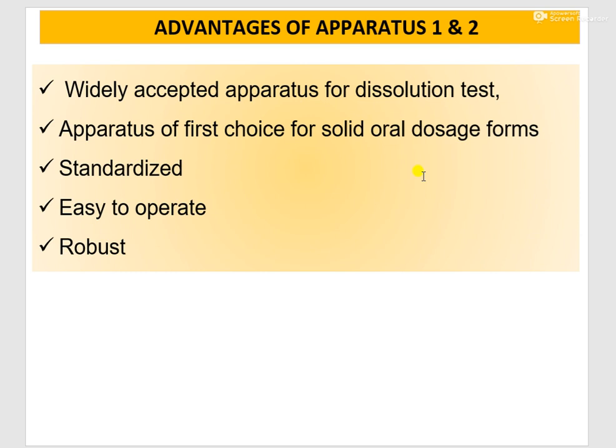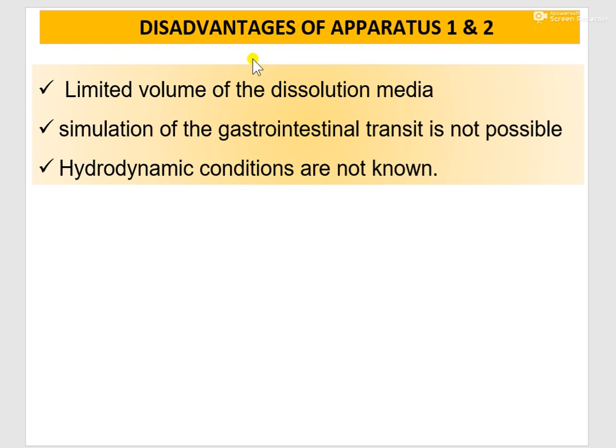Regarding advantages of apparatus 1 and 2: both are widely accepted and commonly used apparatus for dissolution testing, serving as the apparatus of first choice for solid oral dosage forms. They are standardized, easy to operate, and robust. Disadvantages include limited volume of dissolution media, simulation of gastrointestinal transit is not possible, and hydrodynamic conditions are not well known.